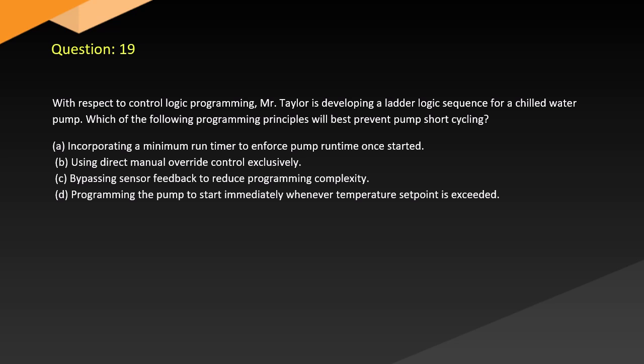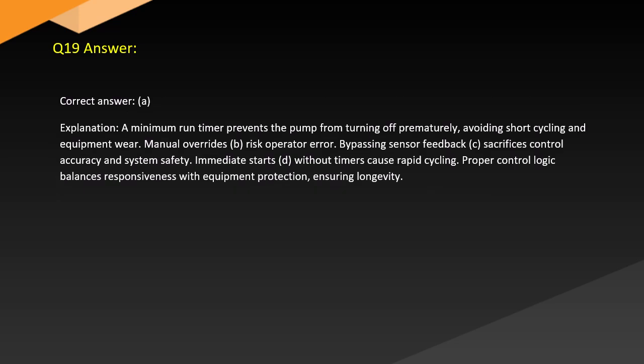Question 19. With respect to control logic programming, Taylor is developing a ladder logic sequence for a chilled water pump. Which of the following programming principles will best prevent pump short cycling? A. Incorporating a minimum run timer to enforce pump runtime once started. B. Using direct manual override control exclusively. C. Bypassing sensor feedback to reduce programming complexity. D. Programming the pump to start immediately whenever temperature set point is exceeded. Answer. Correct answer, A. Explanation.